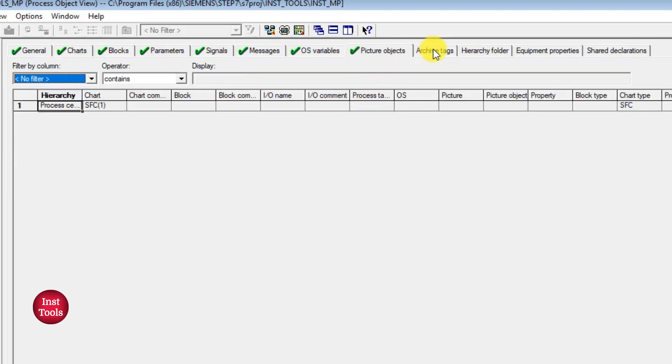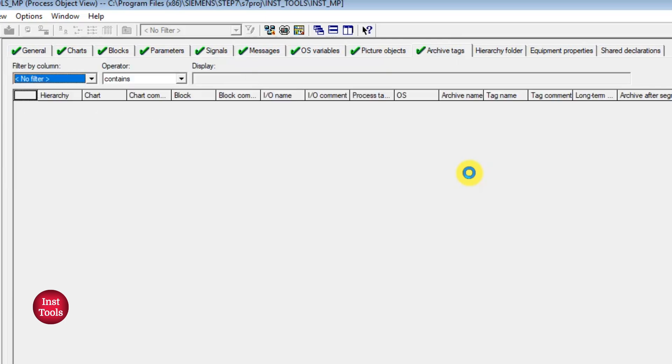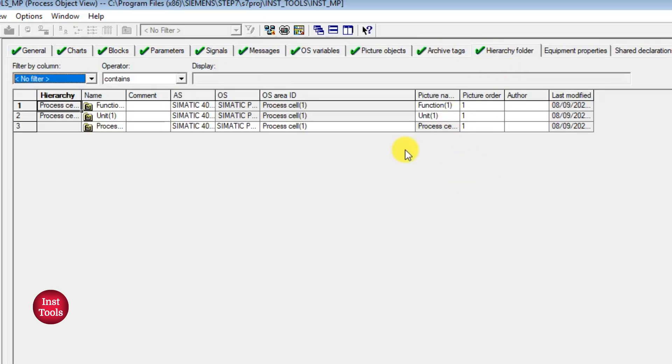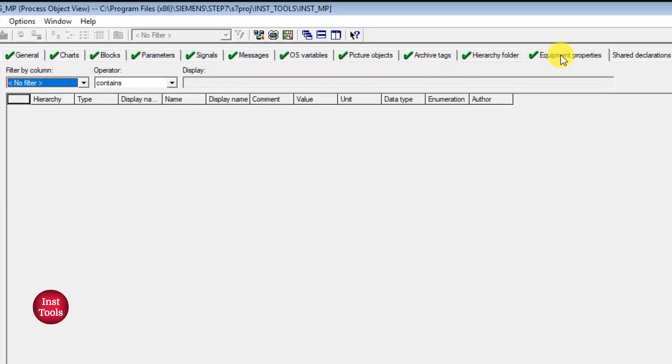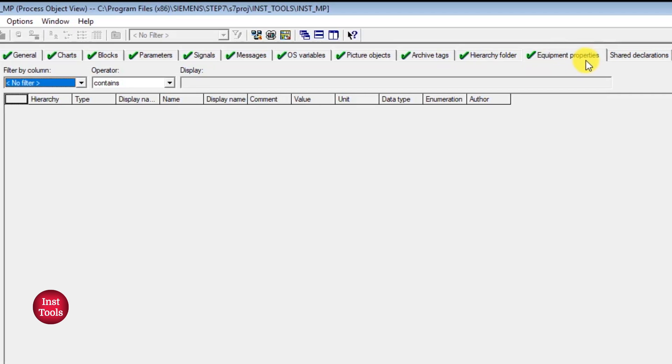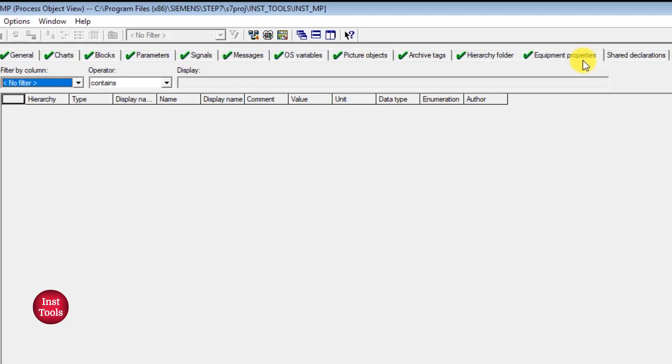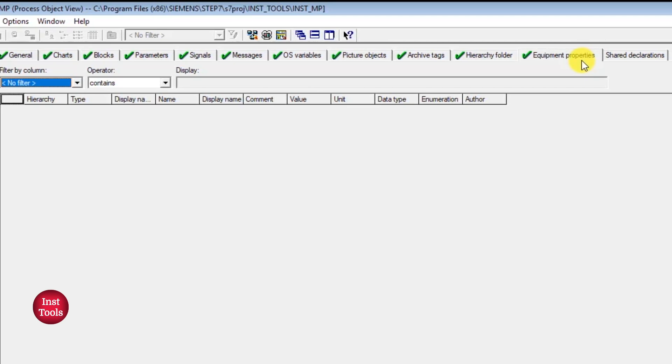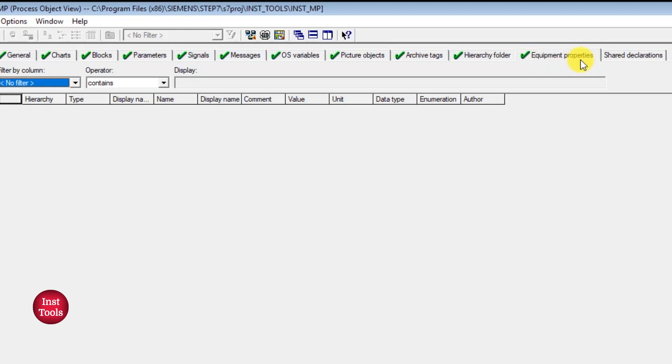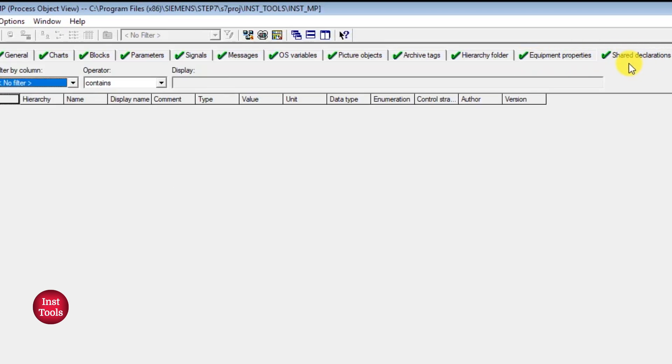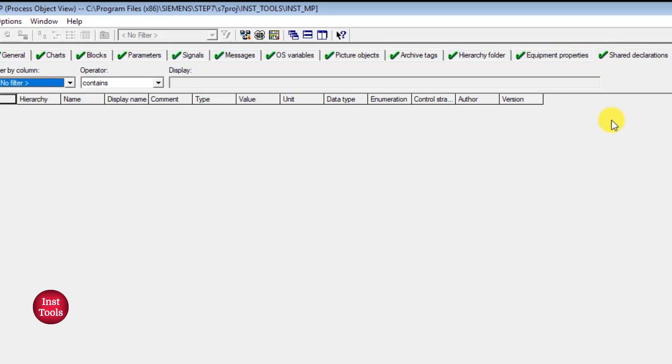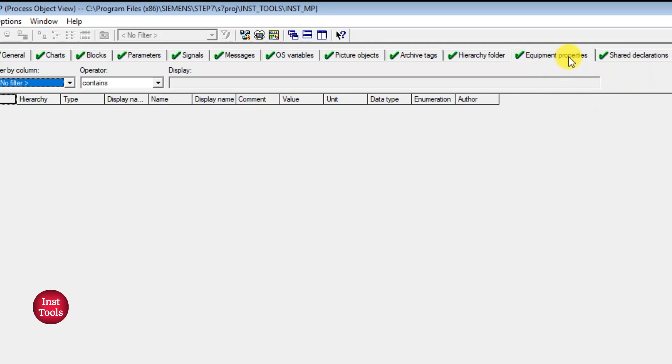What are the blocks inside the project, what are the parameters or like variables we have declared in the project, what are the hardware signals that are coming from hardware configuration of CPU to the project, what are the messages that are configured in the project, what are the variables that are transferred from our Simatic Manager to WinCC will be displayed in OS variables, and what are the icons that we have declared in Simatic Manager will be displayed in picture objects. Because first time it will take time to fetch all the picture objects that we have declared in the project. And next comes archiving. So basically WinCC Classic will be coming with a six months archiving concept. It will work as a historian for a limited time. So we can historize or store the tags with timestamp value for around six months. And what is the plant hierarchy structure, what are the hierarchy folders which we have defined in the project. Equipment properties. So equipment properties in the sense like for example if we have any kind of instruments and we are declaring units for them, so all those units can be configured in the shared declaration.